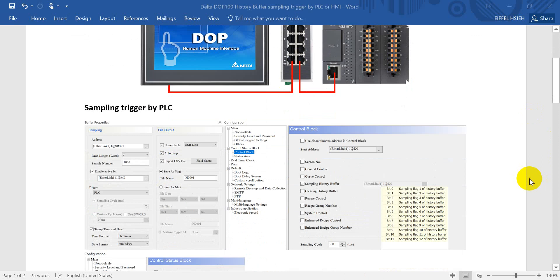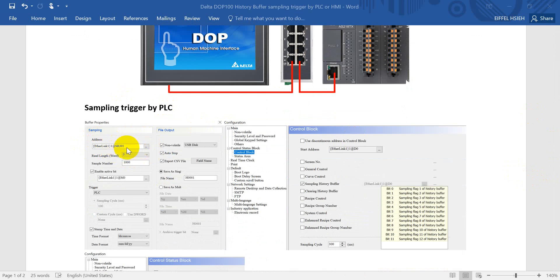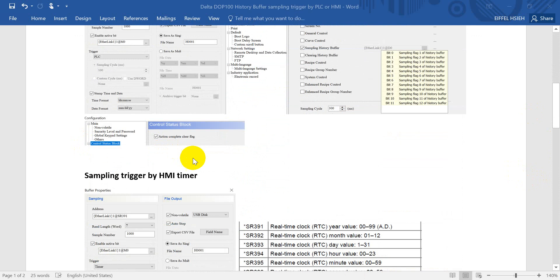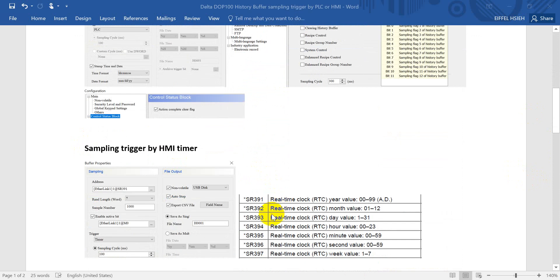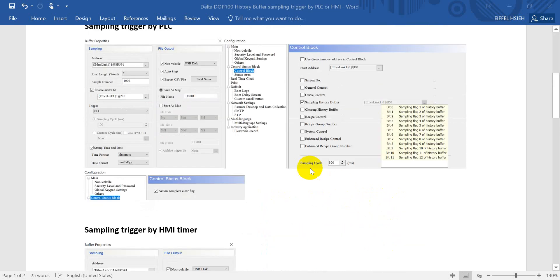You can find the sampling trigger by PLC. First of all, we have to assign the record data, and here we use a special register 391. 391 and 7 words, that means the real-time clock of PLC. It will include year, month, day, hour, minutes, second, and week.